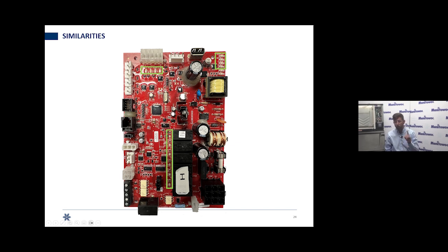For the water probe, there's only one light, and it's corresponding to the high probe. So if that WLP light up at the top there, the second one from the left on the left-hand side, if you've got a trough full of water and the high probe is satisfied, that light will come on. Indigo NXT does have two, one for the low probe, one for the high probe. And we still have the R and L bin lights, but the outputs are all the same. Same bits, top to bottom, what they're supposed to energize and how you would check them.